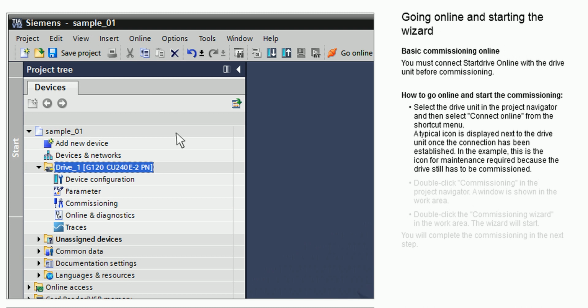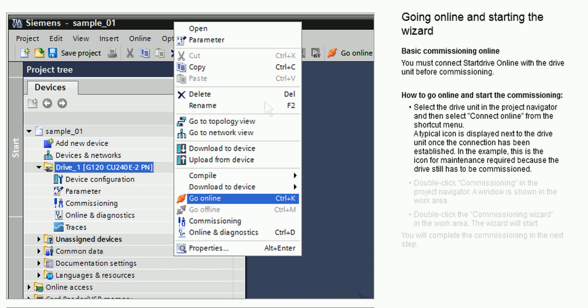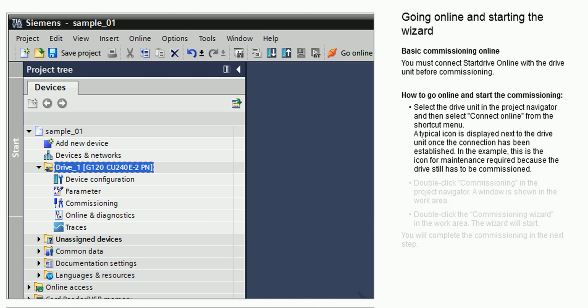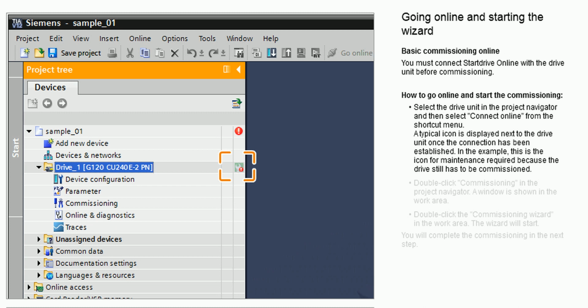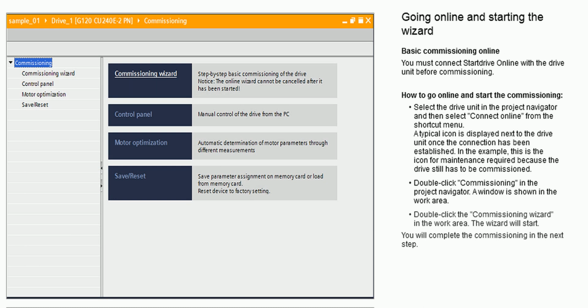How to go online and start the commissioning. Select the drive unit in the Project Navigator and then select Connect Online from the shortcut menu. A typical icon is displayed next to the drive unit once the connection has been established. In the example, this is the icon for maintenance required because the drive still has to be commissioned. Double-click Commissioning in the Project Navigator. A window is shown in the work area. Double-click the Commissioning wizard in the work area. The wizard will start. You will complete the commissioning in the next step.